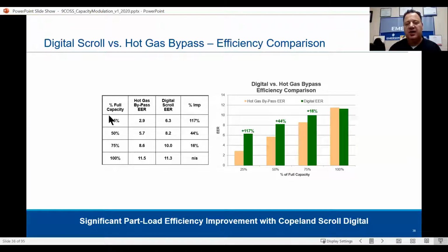So let's take a look at 25% capacity. At 25% capacity, the EER for hot gas bypass is approximately 2.9, or let's just say 3. The digital scroll, on the other hand, is a 6.3. That's a 117% improvement in efficiency in the EER. So that's huge. That's a huge savings. And if you think about some of the bigger stores and multiply how many branches they have, what kind of savings that is annually for all that.